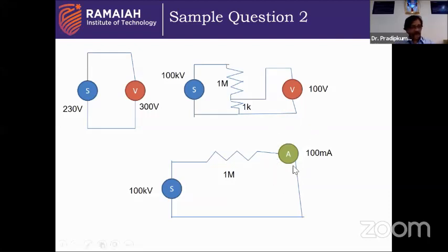I connect a 100 milliampere ammeter in series, and the milliammeter is calibrated to read voltage. The meter scale goes from 0 to 100, but instead of milliamperes, I label it kilovolts. So if I apply 50 kilovolts, the current will be 50 milliamperes, and the needle shows 50, but I read it as 50 kilovolts. Similarly, for 100 kilovolts, 100 milliamperes flow, and I read it as 100 kilovolts.